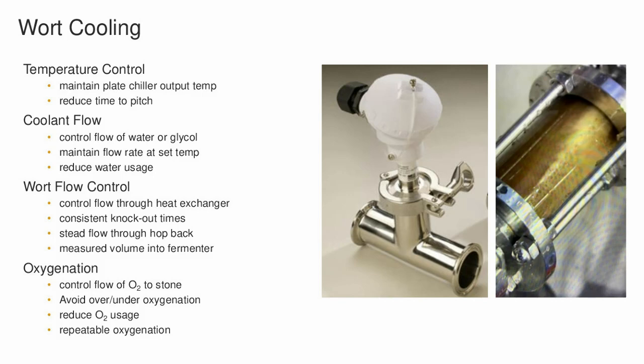Oxygenation - you could certainly control the flow of the oxygen to the stone. There are different feedback sensors, or valves, to monitor and actually adjust that flow of oxygen. It's always a difficult thing with a needle valve, or however you inject it when coming out of the chiller and through an oxygenation stone, to get that just right. Typically it's done by hand and visual. That can still be done, but there are definitely sensors you could utilize to create a control loop.